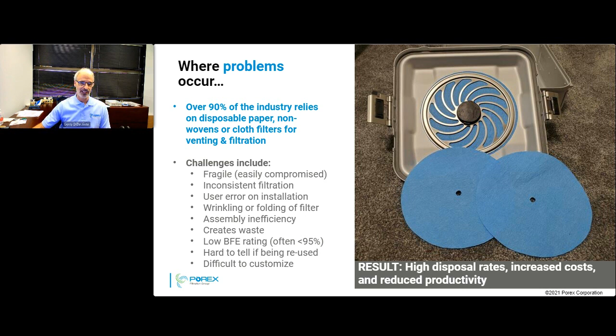And I mentioned earlier, they tend to have a fairly low BFE rating, bacterial filtration efficiency rating, of less than 95%. So if it's exposed to any kind of bacteria, 95% means it's taking 95% out, but that still means 5% of the bacteria is getting through that filter, which is, quite frankly, a scary number.